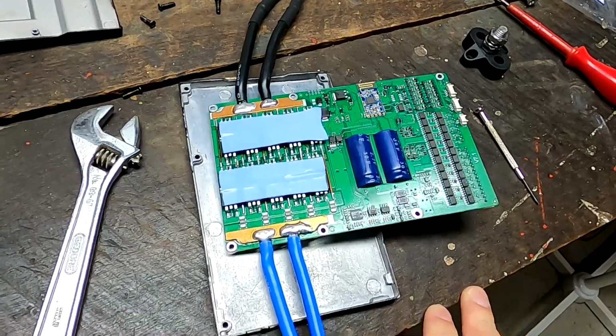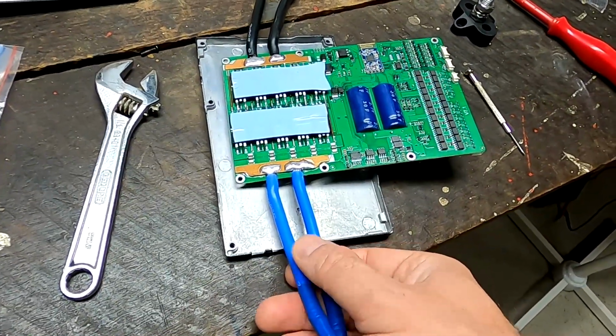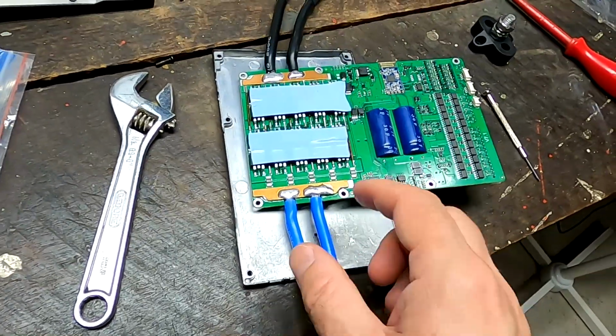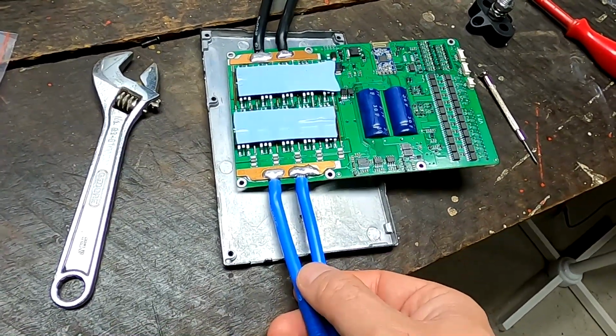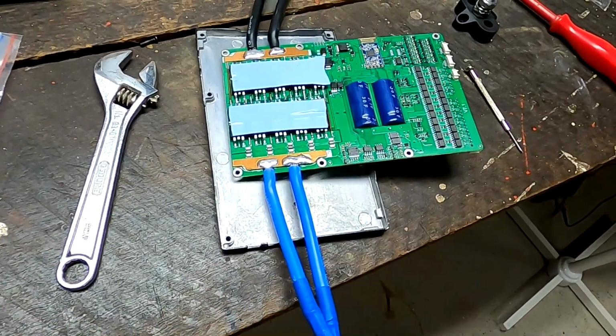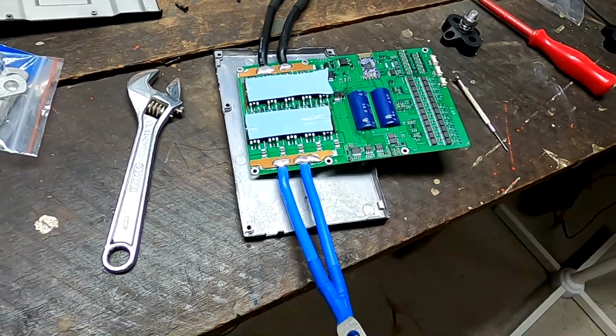So the cables are only half as strong as they should be. To carry 200 amps, it should be a 2 gauge or a 35 millimeter cable. But we are far away from that. I don't know, they're building all these nice BMSs in China, but they're always undersizing the cables. Probably because these cables are the most expensive part on these boards.